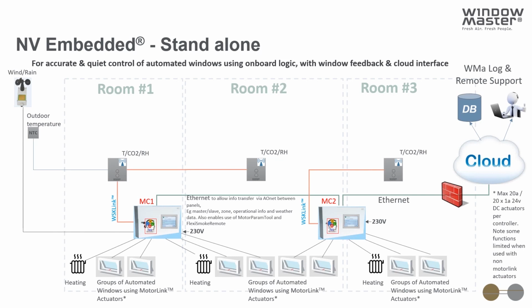Typical system topology for NV Embedded as a standalone system will have room temperature sensors, CO2 sensors wired back to the controllers, independent groups of windows around the spaces in different rooms, which can exhibit a high level of independent control for each group of windows, and a weather station. The onboard intelligence within the controller will optimize the vents it's looking after, and the whole system is networked together to share things such as time and weather data, and it's connected to the cloud so we can look at cloud-based data aggregation and user interfaces.